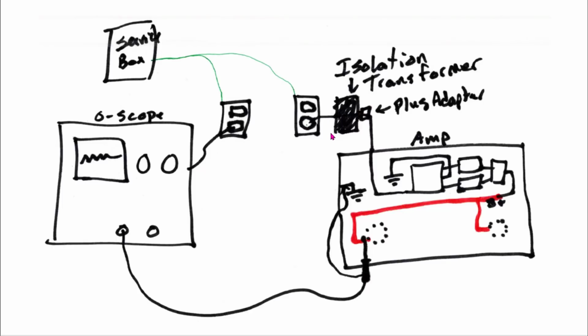One thing I would not recommend: some people will say, well, there's an easy way to solve for that, Mark. I'll just put my oscilloscope on an isolation transformer. That way it's always isolated from the earth ground, and I never really have to worry about it conflicting with the ground and the device under test here, the DUT.